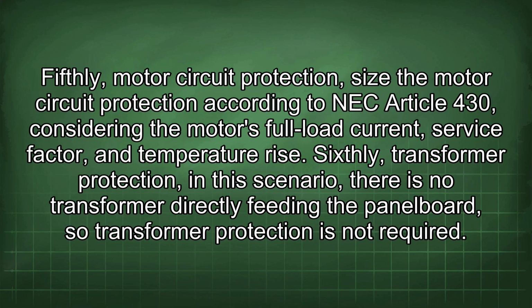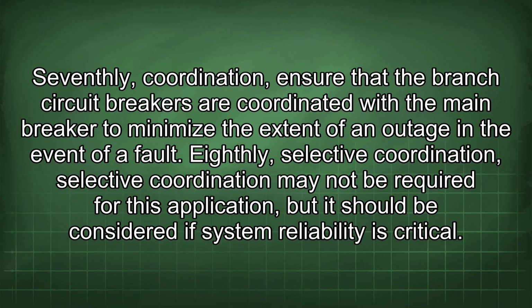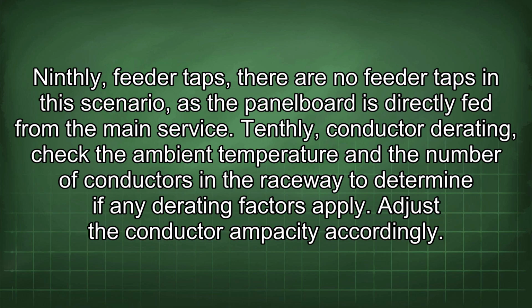Fifthly, motor circuit protection. Size the motor circuit protection according to NEC Article 430, considering the motor's full load current, service factor, and temperature rise. Sixthly, transformer protection. In this scenario, there is no transformer directly feeding the panel board, so transformer protection is not required. Seventhly, coordination. Ensure that the branch circuit breakers are coordinated with the main breaker to minimize the extent of an outage in the event of a fault. Eighthly, selective coordination. Selective coordination may not be required for this application, but it should be considered if system reliability is critical. Ninthly, feeder taps. There are no feeder taps in this scenario, as the panel board is directly fed from the main service.